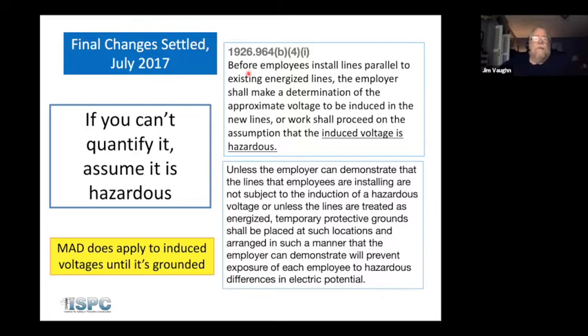And these de-energized circuits that are subject to induction are also subject to MAD. And we have an OSHA rule, effective in 2017, that says the employer must calculate the level of induction. And if you can't calculate it, which is a graduate level calculation, you can't do it on the crew or on the job. But if you can't calculate the voltage level that's going to be on the lines, you have to assume that it's hazardous. And you do need to do that. There are two forms of induction that we detail and study in our grounding class that we're not going to take the time to do here, but there are numerous instances where induced voltages will kill you if you don't respect it. You must treat these de-energized circuits where they're subject to induction as energized, and MAD does apply until you have properly grounded and bonded the worker in where induction is a risk.